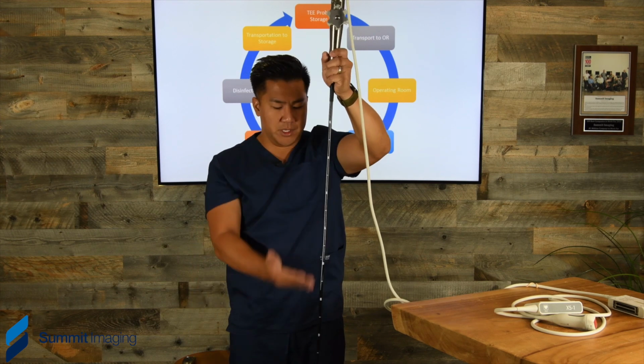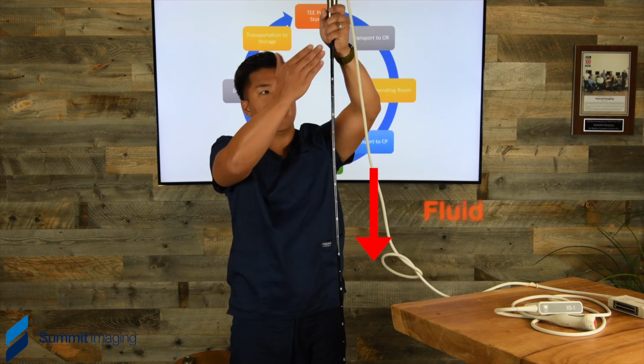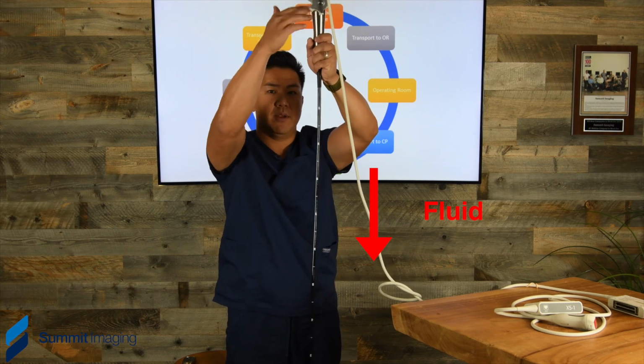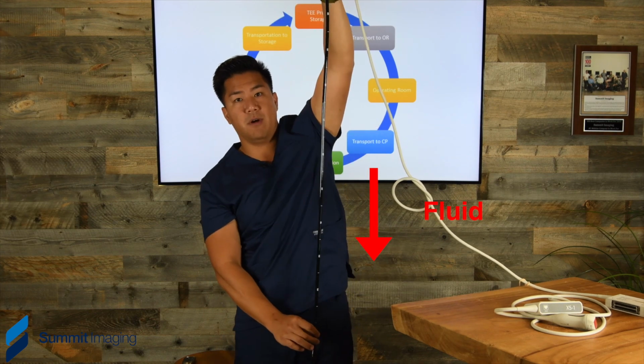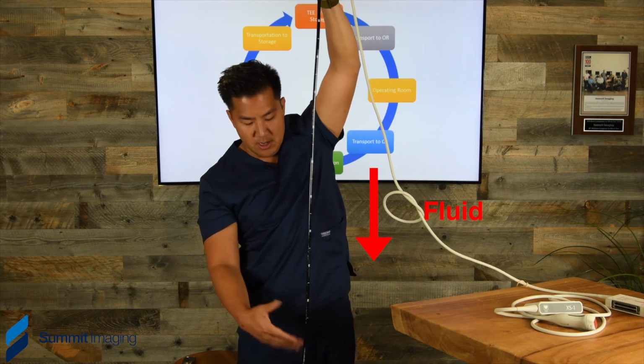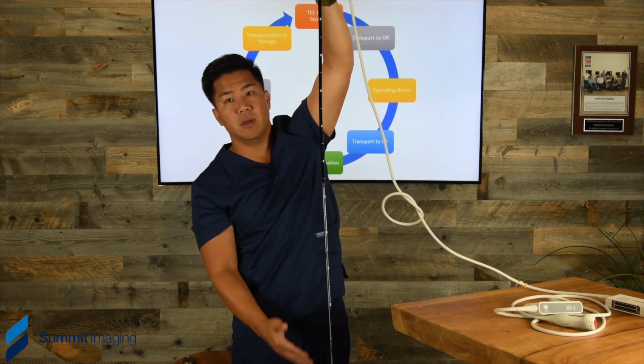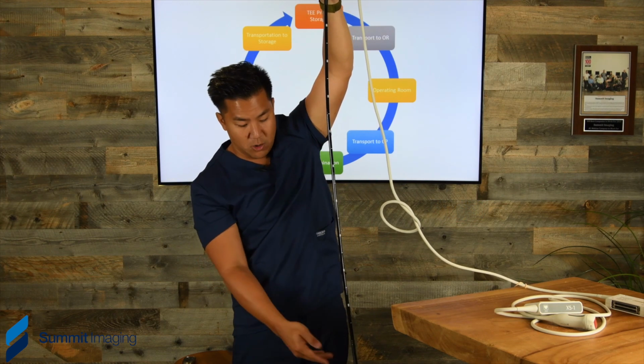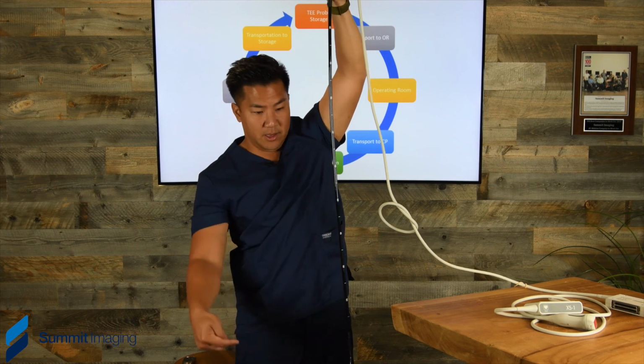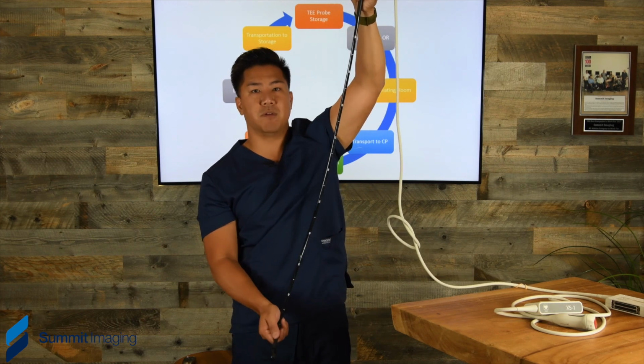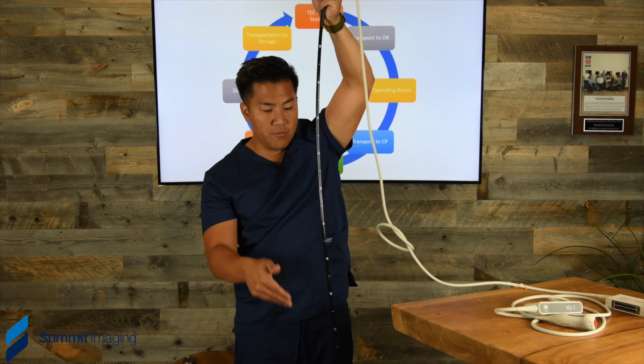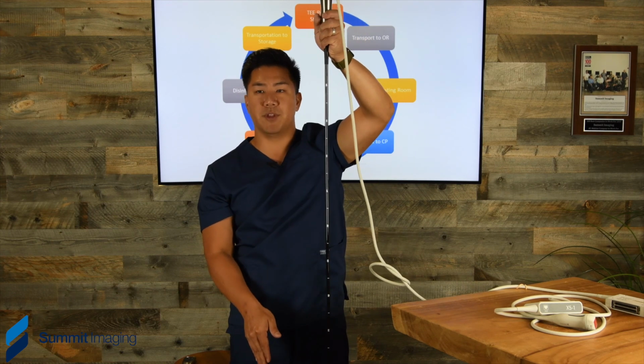But guess where all that fluid's going? It's actually running down the tube. If it's penetrated from the handle or from the bending rubber, it's all going to cascade down into the crystal. And guess what - the highest concentration of fluid is going to move to the most sensitive part of this transducer.